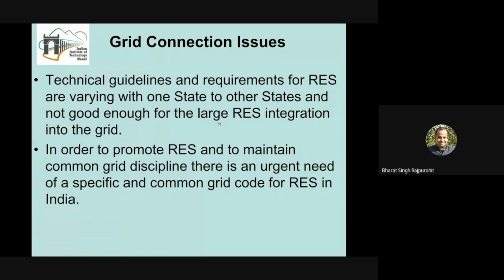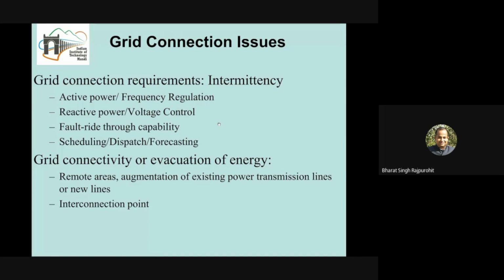What is the grid connection issue? The grid connection issue is that whenever a new source or new load is getting connected to the power grid, it should also have certain responsibilities. They should follow a certain mechanism. They should follow certain codes, so that the system is maintained with proper stability and reliability. So grid codes are known as the technical guidelines and requirements for the renewable energy sources, which need to be followed. Fine. So this is what is known as grid codes.